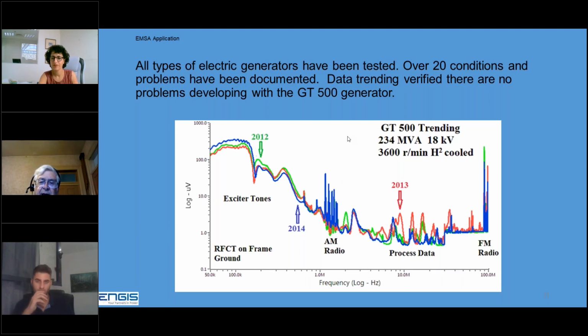At this petrochemical site down in Louisiana, gas turbine 500, here's data from 2012 in green, 2013 in red, 2014 in blue. Really nothing going on. We like radio stations. They make very good benchmarks. So when you see very strong radio stations versus what's coming out of the rest of the system, it verifies there's no problem with that generator or transformer.